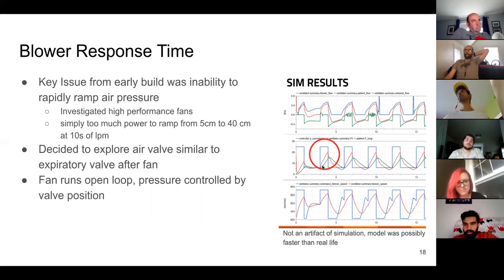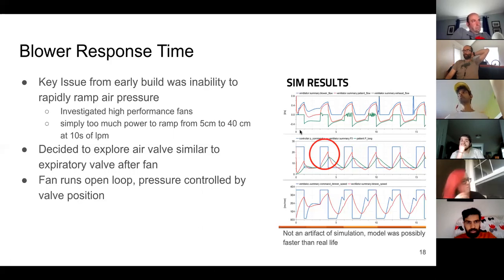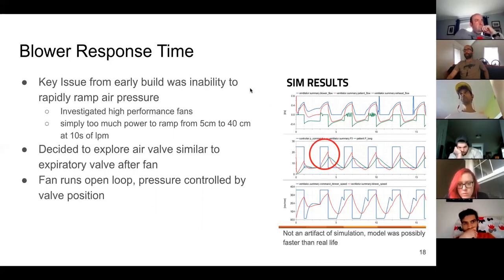What you're basically seeing is that the command pressure was up at like 24 centimeters, and during that breath time, the pressure wasn't getting anywhere close. This isn't an artifact of simulation, we validated this with both the breadboard models and the integration model. The fan at 12 volts just couldn't put enough power through it to accelerate flow that quickly. So we looked at a bunch of different fans and the supply chain for them, and concluded that ramping the fan was going to be a harder problem than adding a valve after the fan. So that's what we decided to do.